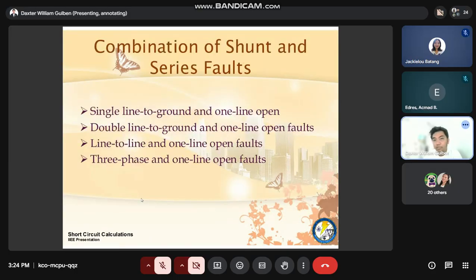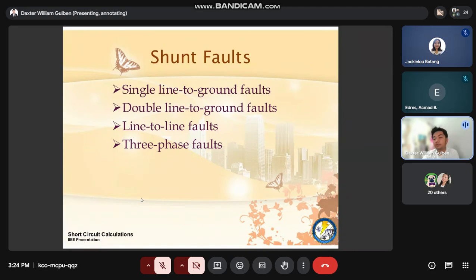There is also a combination of shunt and series fault. It can be a single line to ground and one line open. It can be double line to ground and one line open. It can be line to line and one line open. Then a three phase fault at the same time with one line open. Dealing with these different types of fault, the analysis is more complicated. But for the purpose of this class, we just need to discuss the shunt faults. These are the common ones.